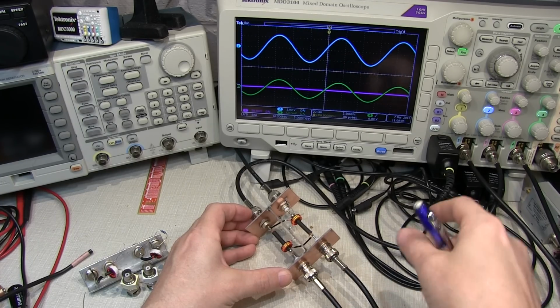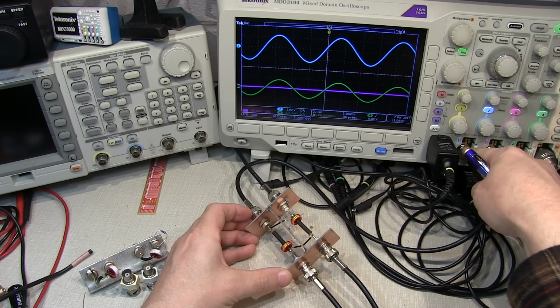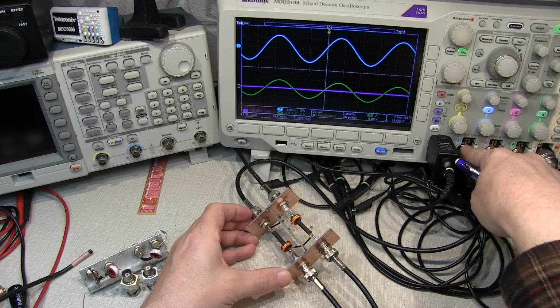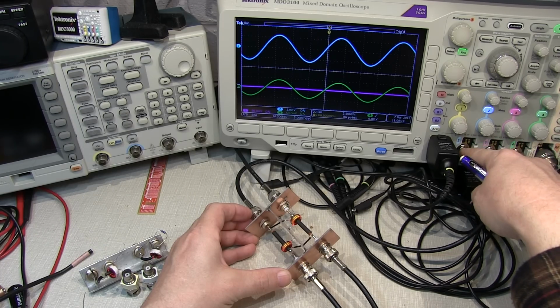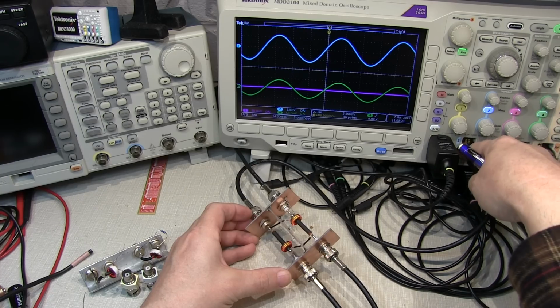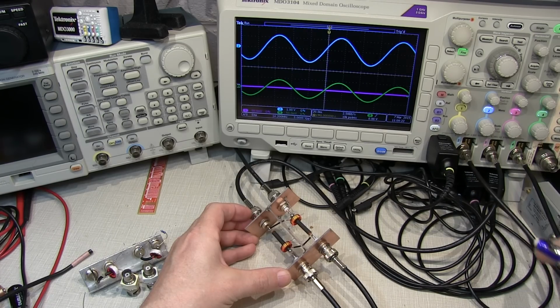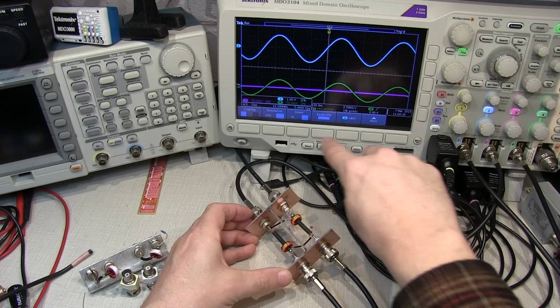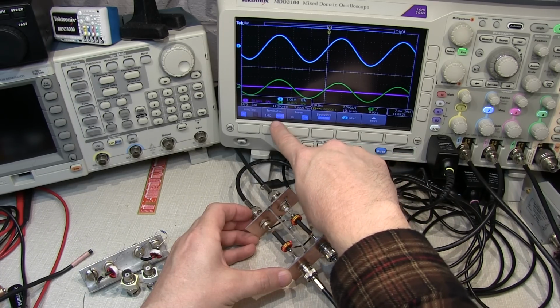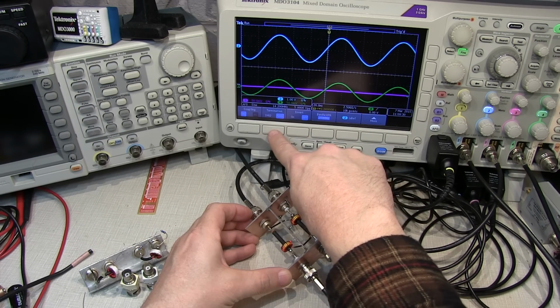If we mis-terminate this line, we disturb the impedance match. For example, if I change the termination impedance on channel 2 from 50 ohms to say 1 megohm, that creates an impedance mismatch, and we'll reflect energy, nearly all of the voltage, back from this port and through the other direction. Let's turn on channel 2 and change its termination from 50 ohms to 1 meg, and watch what happens.